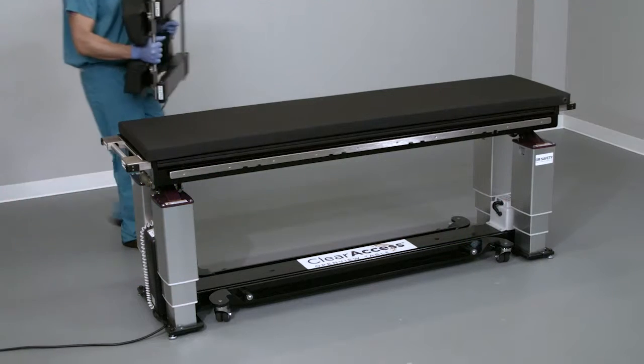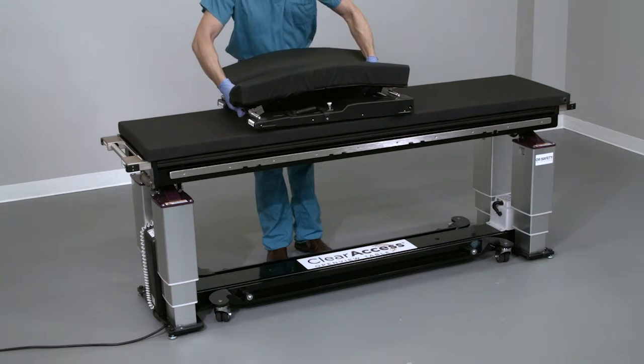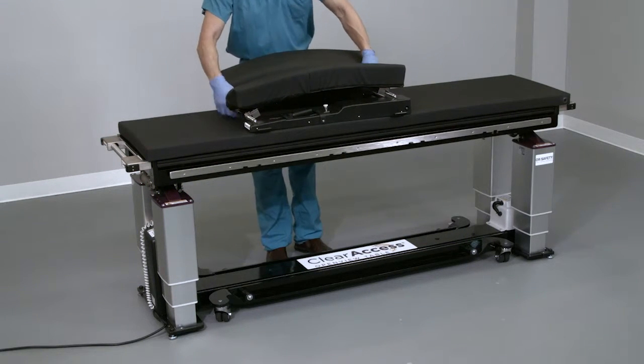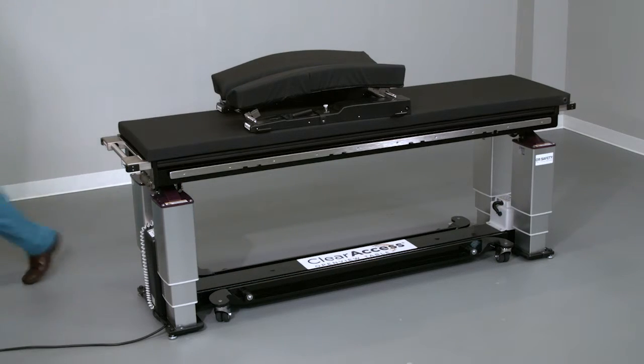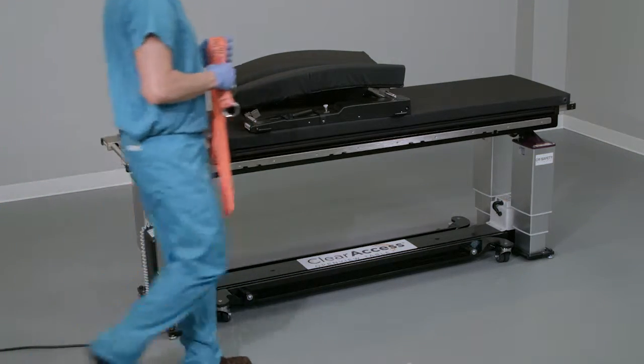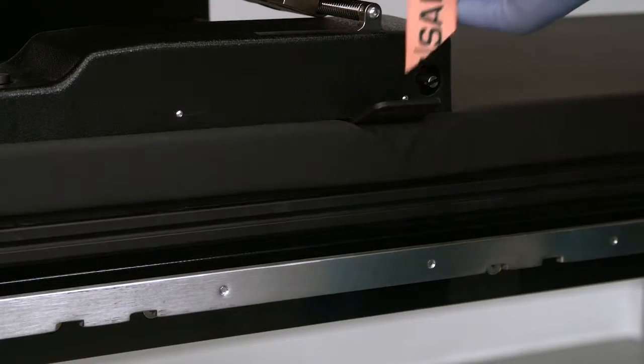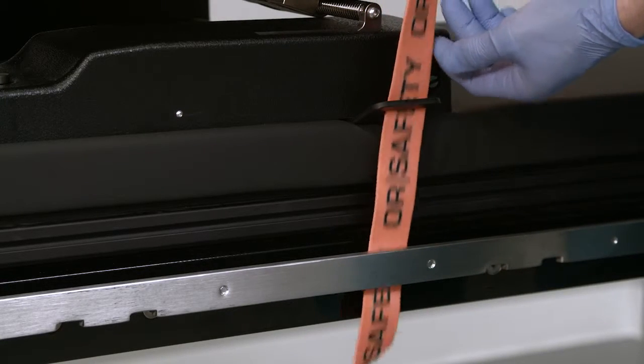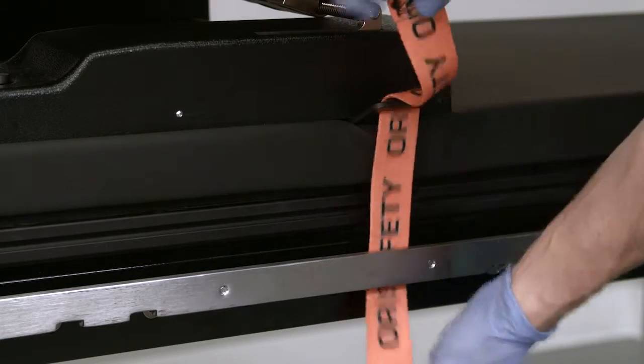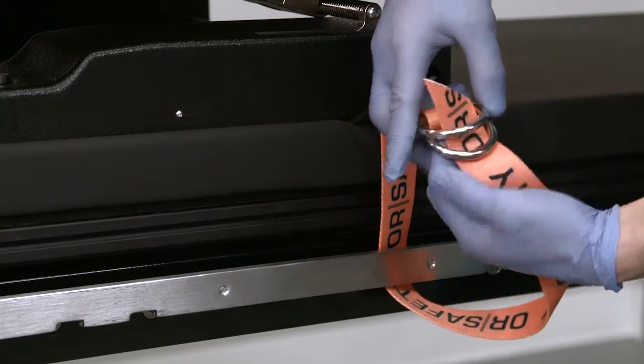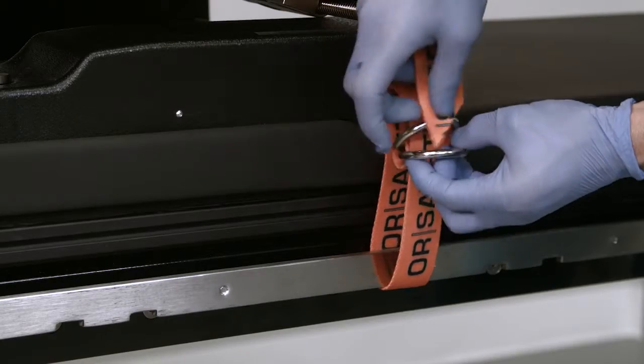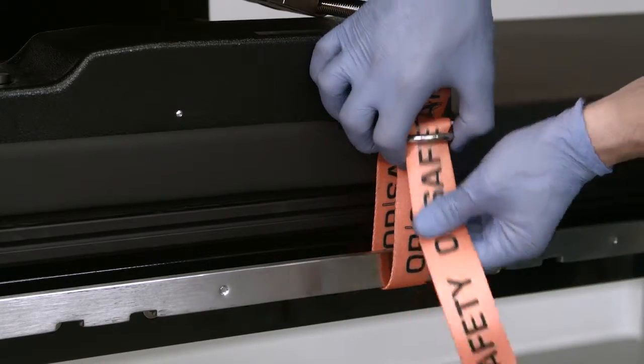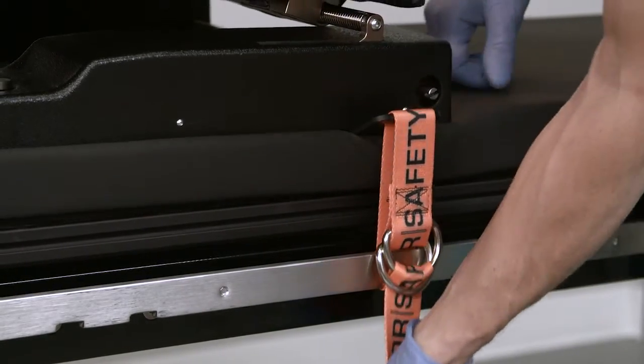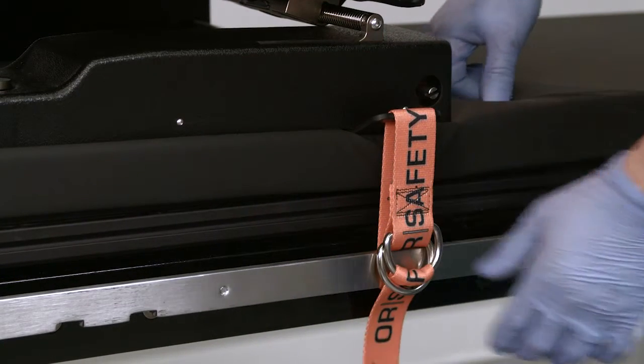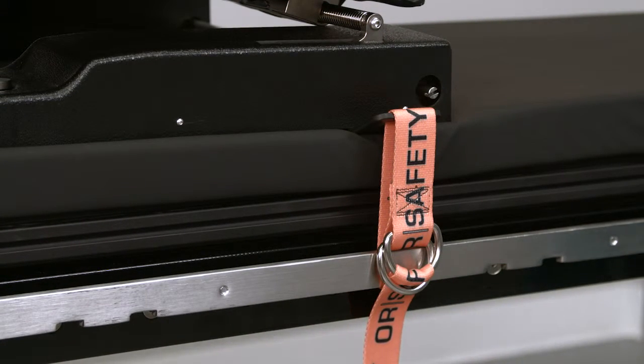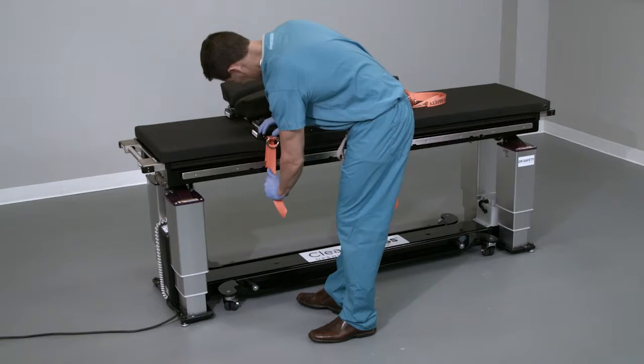To install the FlexFrame, place it in the desired location for the patient's torso during the procedure, leaving enough room at the head end of the table for the patient's head and supporting face pillow. Secure the FlexFrame to the table using all 4 orange safety straps, one at each corner of the FlexFrame. With each strap, run the strap through the foot of the FlexFrame, down and around the continuous side rail of the Clear Access table, and then back up and through the D-ring of the safety strap. Pull down firmly to ensure that the FlexFrame is securely fastened. Repeat with the remaining 3 safety straps.